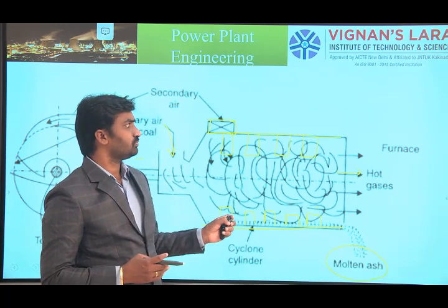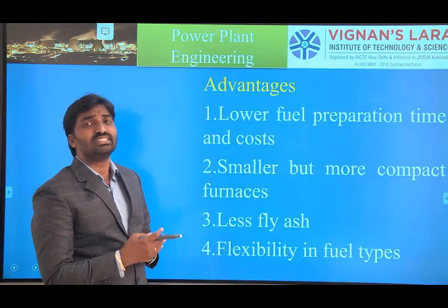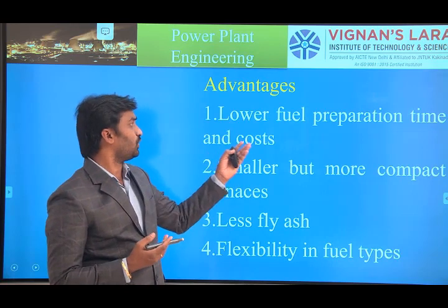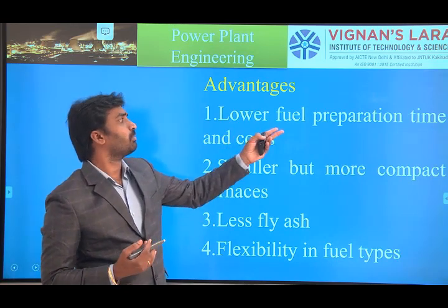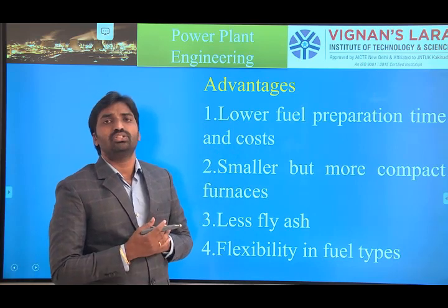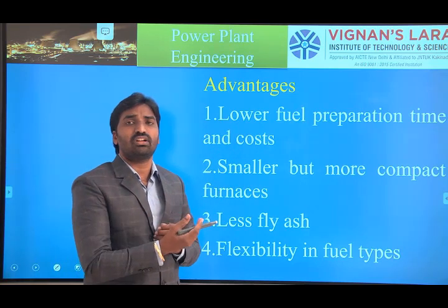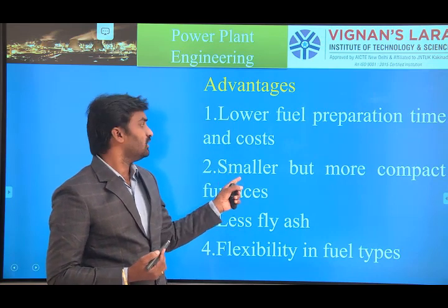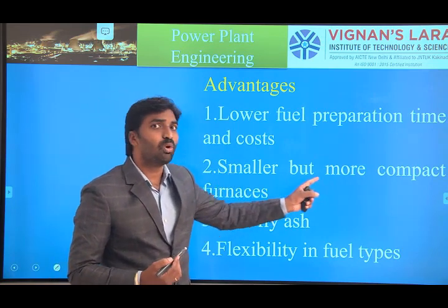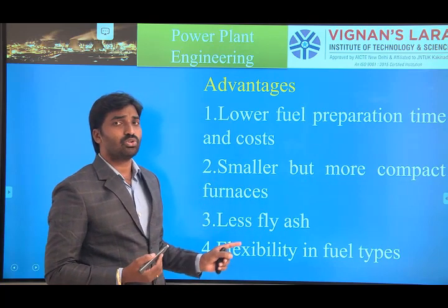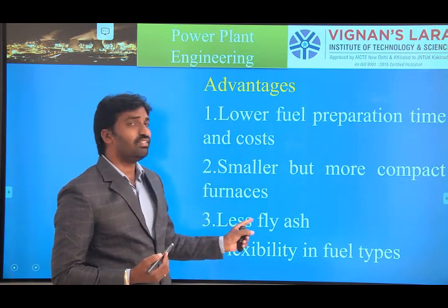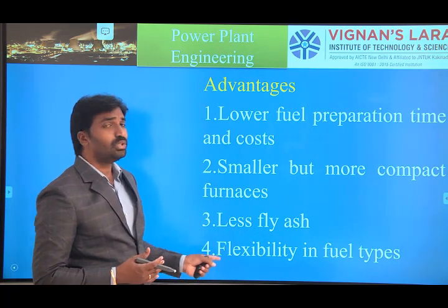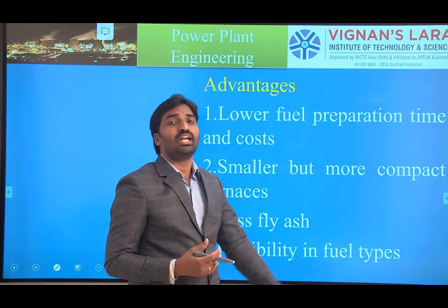And what are the advantages of a cyclone furnace? A cyclone furnace gives proper combustion of fuel and lower fuel preparation time and cost. The cyclone furnace is smaller in size but more compact in nature, it has less fly ash content, and it is also flexible with different types of fuels.